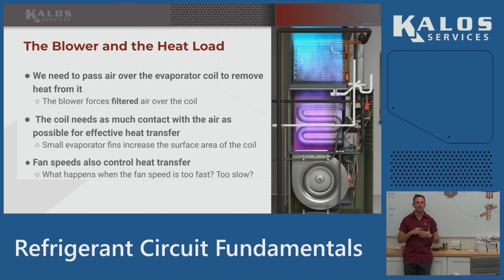If I have too much airflow, I'm going to see a higher suction pressure. If I have not enough airflow, I'm going to have a lower suction pressure. So generally, when we do installs, we like to set speed 2 on your normal ECM motor for cooling, and we like the 4 for the heating mode, because you want more airflow when you're heating than when you're cooling. When you're cooling, I want lower airflow, yes.